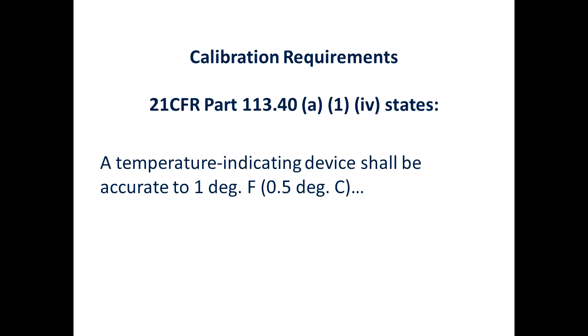The standard goes on to state that a temperature indicating device shall be accurate to 1 degree F or ½ degree C. And the old standard, if you remember, just said that your MIG had to be accurate. And now they have put a number on here. The specification for our Digi-Stem system at the temperatures that most of you process at, up to 300 degrees F or below, is 0.3 degrees Fahrenheit. So it exceeds the specification of the standard, but the standard is 1 degree Fahrenheit.